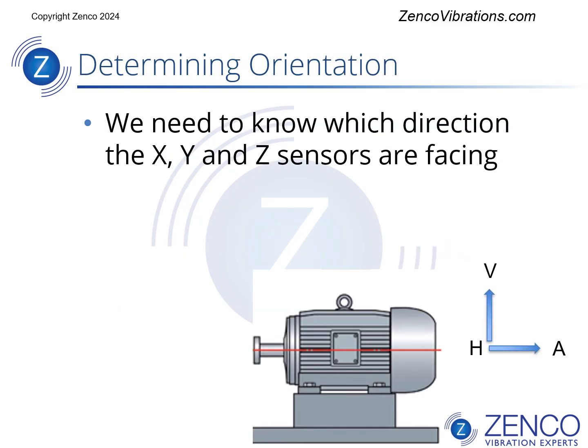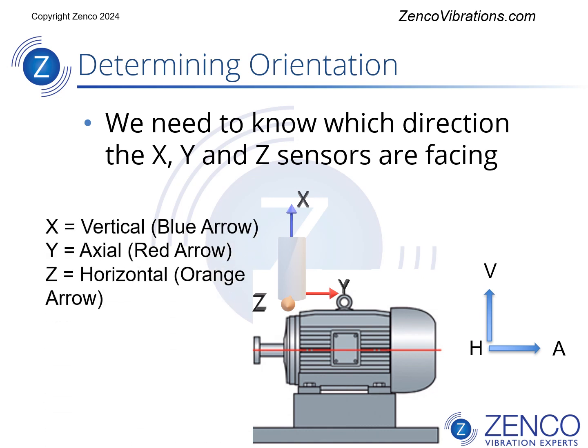Here's an example of a horizontal machine — we're going to define the orientation of this sensor. In this case, the X sensor with the blue arrow is pointing in the vertical direction, the Y sensor with the red arrow is pointing in the axial direction, and the Z sensor with the orange arrow is pointing towards us, or horizontal. We would define this orientation as V, A, H. So instead of X, Y, Z, the first channel X is V, the second channel Y is A, and the third channel Z is H.